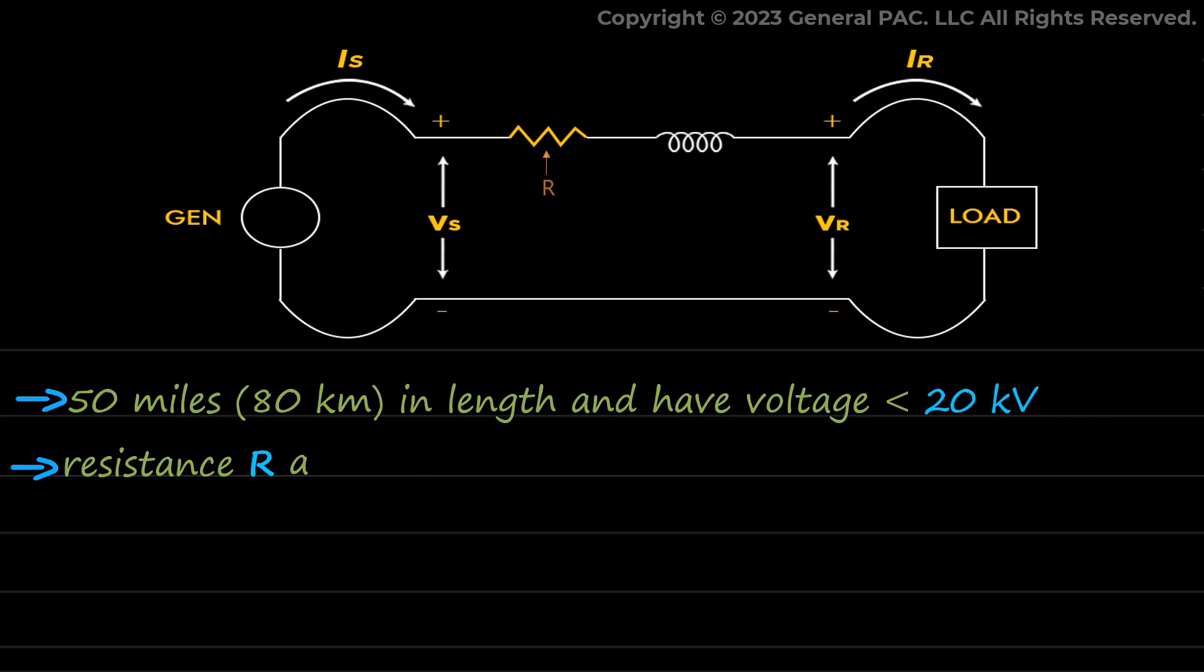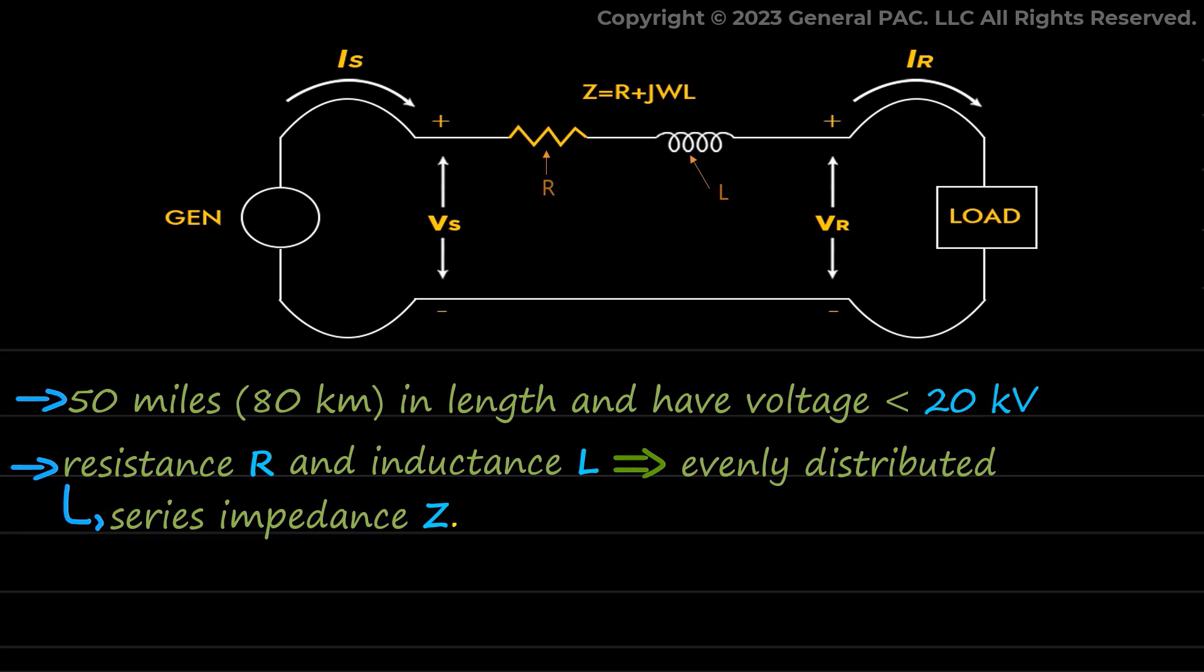The resistance R and inductance L are considered to be evenly distributed along the line shown as series impedance Z. Shunt capacitance, although present, is so small that it is considered negligible and omitted without much effect on accuracy. This makes it easier to understand and model short lines.